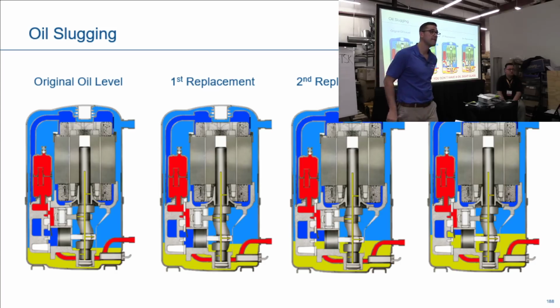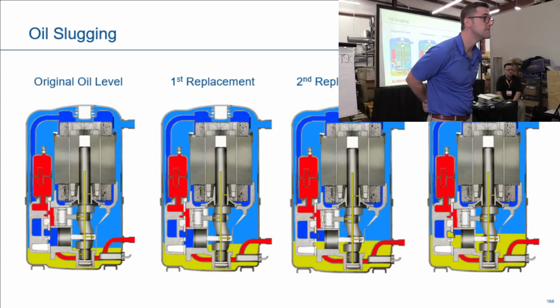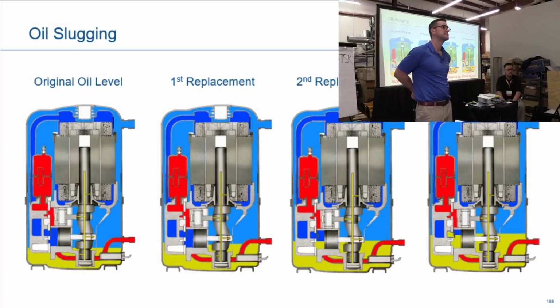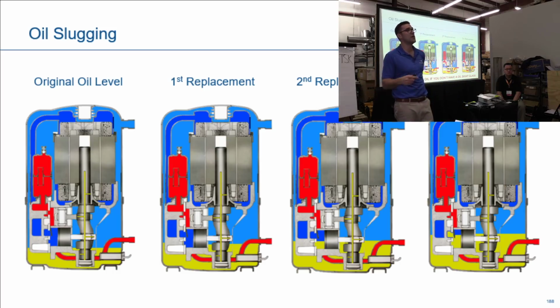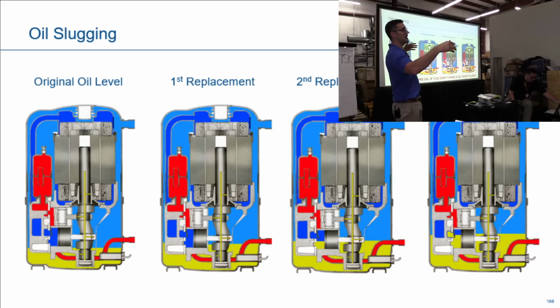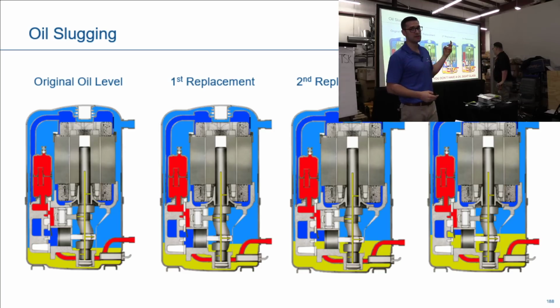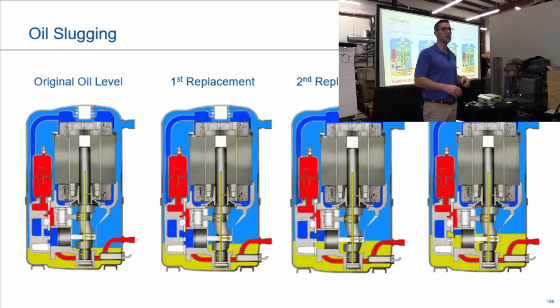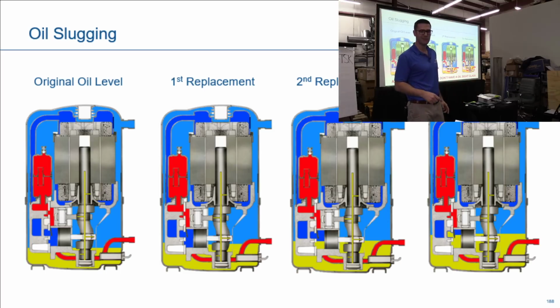What would be an efficient way to withdraw all that oil from the system? Well, it depends where it's at. I was at one application. Well, we were doing a job and there were 4 coils in this walk-in box. It was a cooler box. 3 coils working perfectly. The 4th one wasn't, no temperature on it. So we pumped it down, and my journeyman at the time, because I was a young mechanic, he says, "Trevor, get me a drill." I'm like, "What are you talking about, a drill?" He takes a drill, drills it right through the coil. All of a sudden the oil started pouring out.